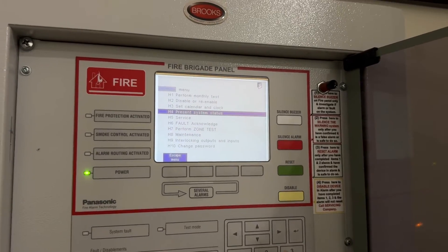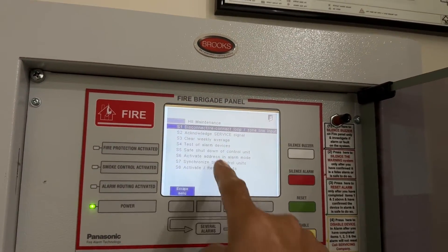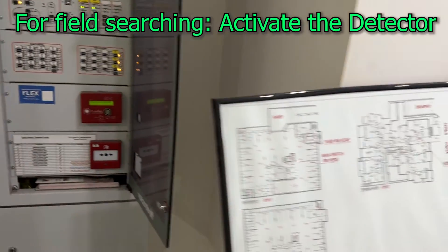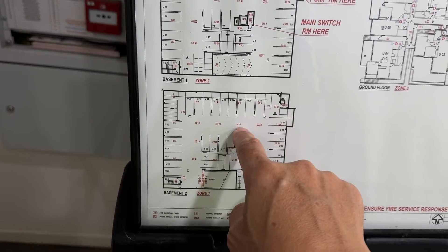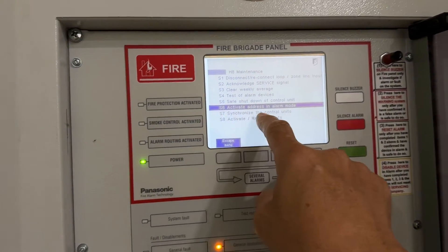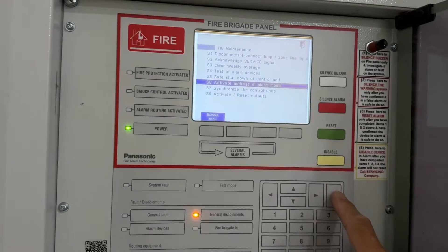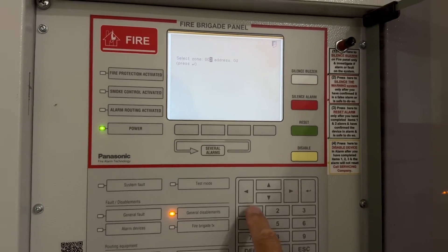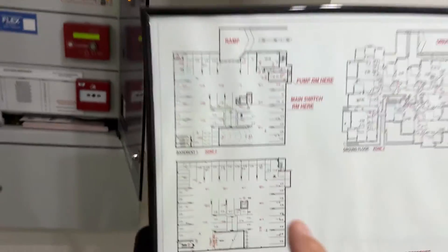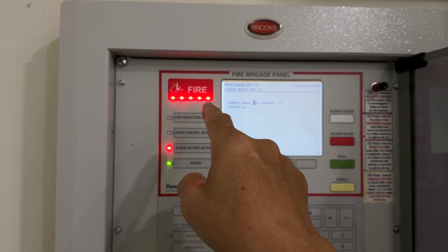Sensor values of 17 - let's not go further than that. Let's do service, H5. Now let's activate that detector, H8, Enter. Activate alarm mode - this is one way to find out the detector if the floor plan is not right. According to the plan it's 17. Let's check downstairs if Detector 17 is in that spot. Let's activate alarm mode first, Enter. Everything is isolated - occupant warning isolated, ASC is isolated. Zone one, address 17, Enter. We got an alarm but there's no noise. So let's go downstairs and search for Detector 17. Because it's on alarm, that detector's LED red light should be on.